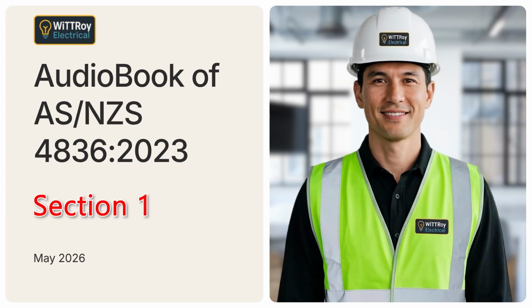Clause 1.4.40. Testing. Testing means using test instruments or test equipment by a competent person. The key point is that testing must be done by someone who understands the test, the equipment, the limits, and the safety risks. Clause 1.4.41. Voltage. Voltage means the difference in electrical potential that normally exists between conductors, or between conductors and earth. In practical terms, voltage is what can drive current through a circuit, or through a person if unsafe contact occurs.